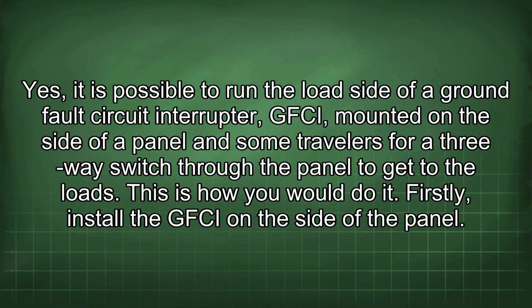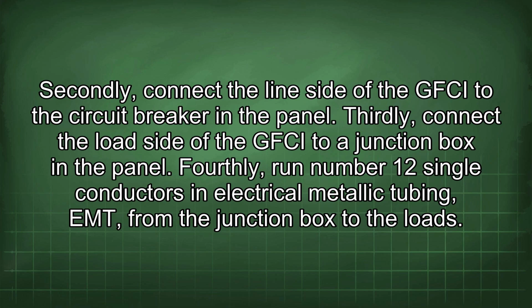Firstly, install the GFCI on the side of the panel. Secondly, connect the line side of the GFCI to the circuit breaker in the panel. Thirdly, connect the load side of the GFCI to a junction box in the panel. Fourthly, run number 12 single conductors in electrical metallic tubing (EMT) from the junction box to the loads.